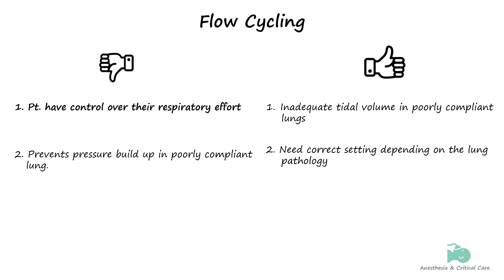For instance, in patients with poorly compliant lungs, the flow decreases swiftly, prompting the ventilator to cycle to expiration and thus preventing pressure buildup in the lungs. However, patients with poor lung compliance may experience inadequate tidal volumes, leading to insufficient minute volume. Incorrectly low settings could cause uncomfortably deep and prolonged inspiration, while excessively high settings might result in double triggering due to insufficient inspiratory time. Overall, flow cycling requires a good understanding of the patient's respiratory physiology and the cycling settings on the ventilator for better patient comfort and outcome.